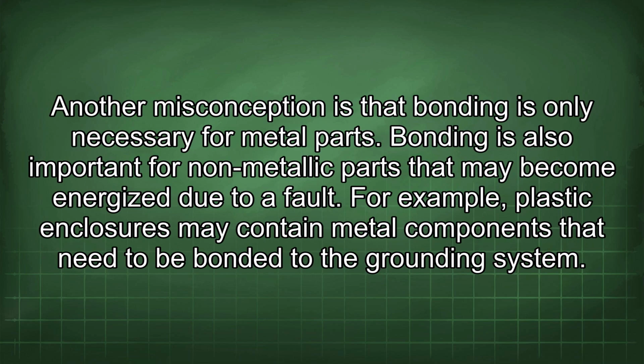Another misconception is that bonding is only necessary for metal parts. Bonding is also important for non-metallic parts that may become energized due to a fault. For example, plastic enclosures may contain metal components that need to be bonded to the grounding system.